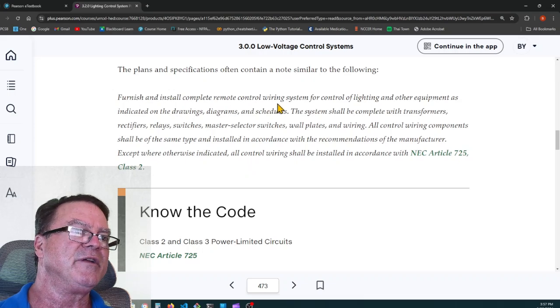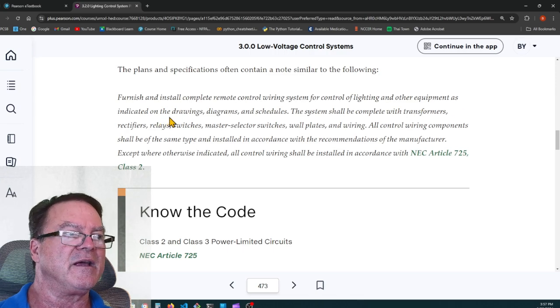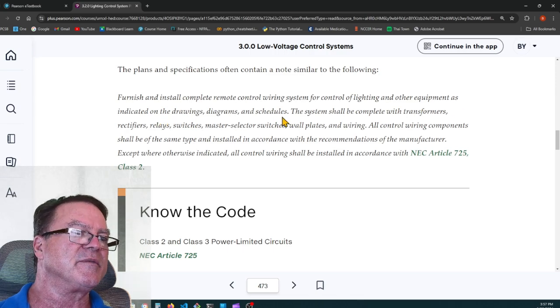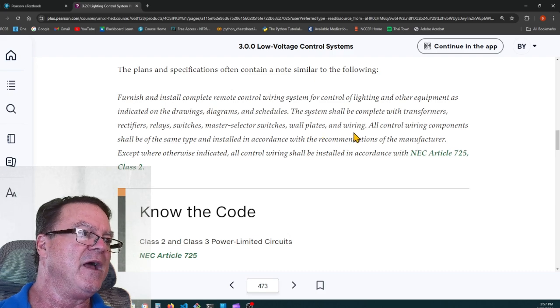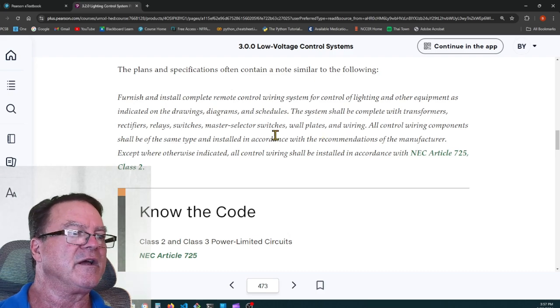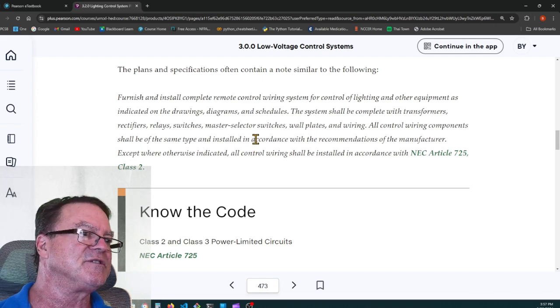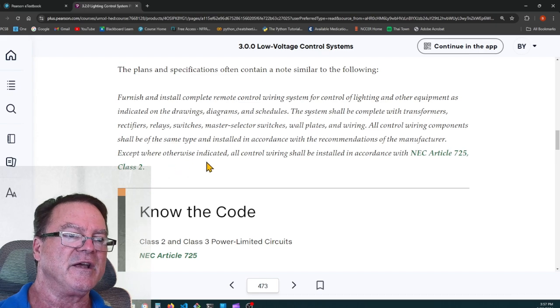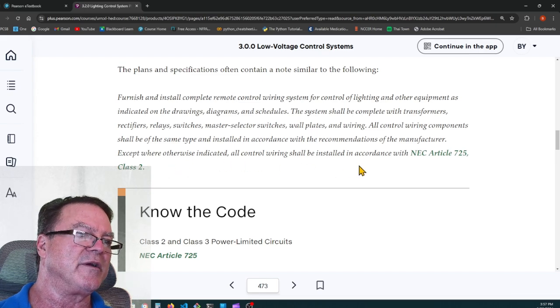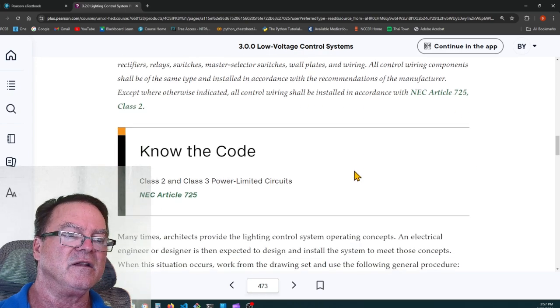Furnish and install complete remote control wiring system for control of lighting and other equipment as indicated on the drawing, diagram, and schedules. The system shall be complete with transformers, rectifiers, relays, switches, master selector switches, wall plates, and wiring. All control wiring components shall be of the same type and installed in accordance with the recommendations of the manufacturer, except where otherwise indicated. All control wiring shall be installed in accordance with NEC Article 725, Class 2.